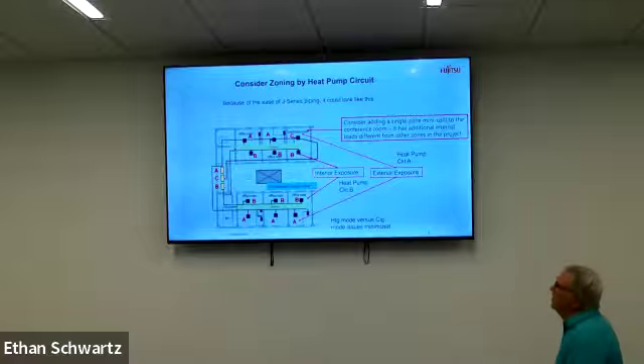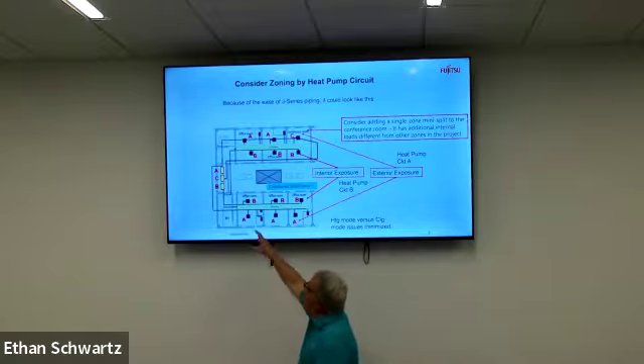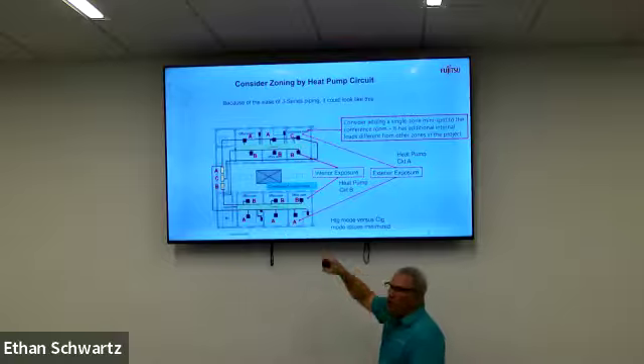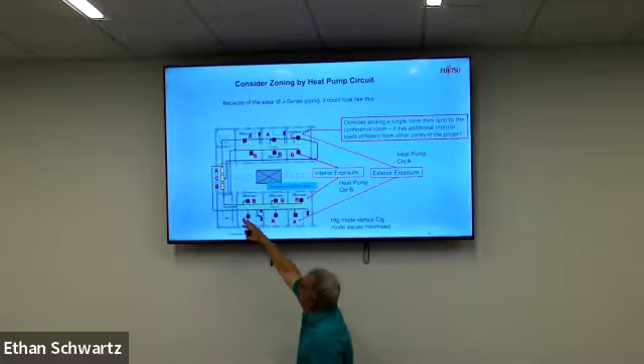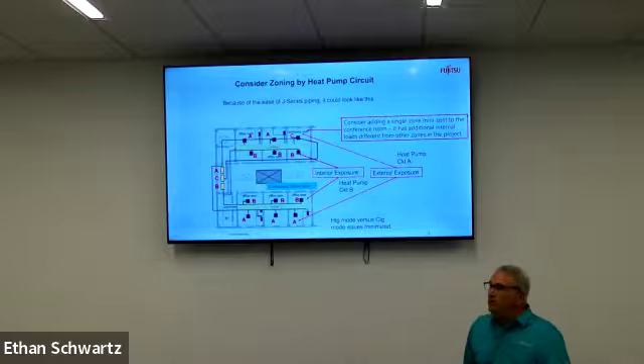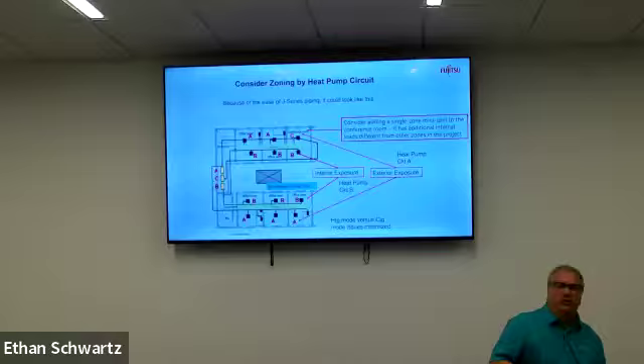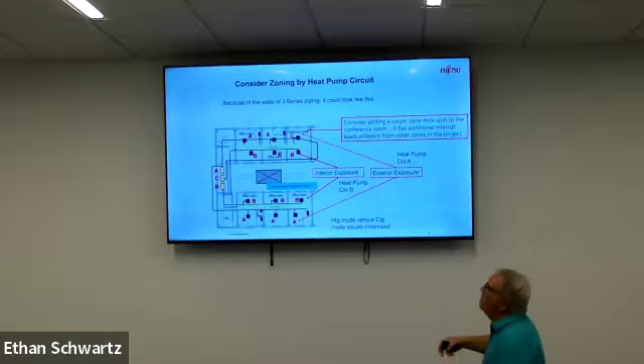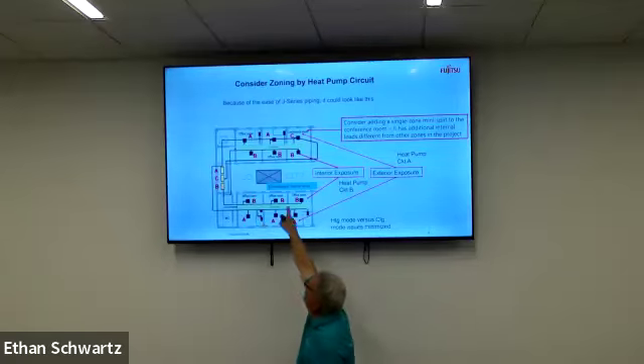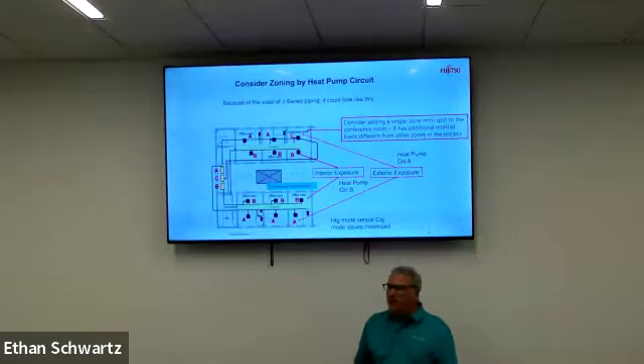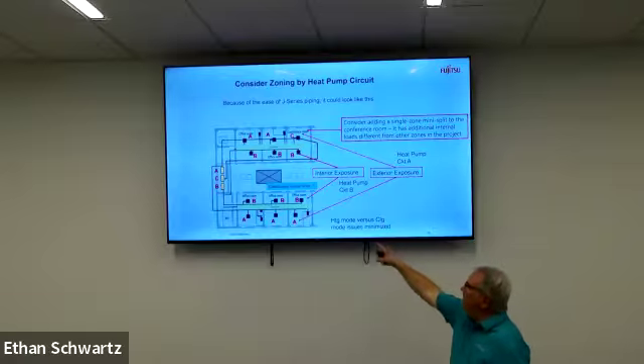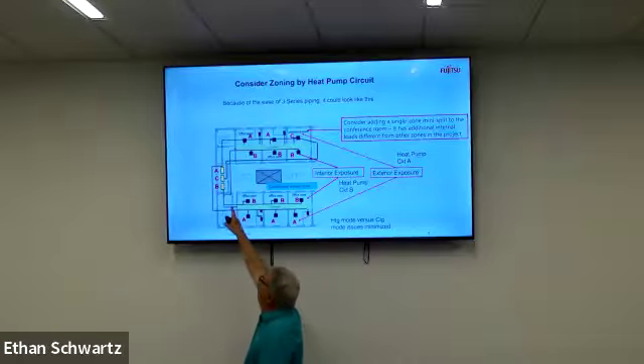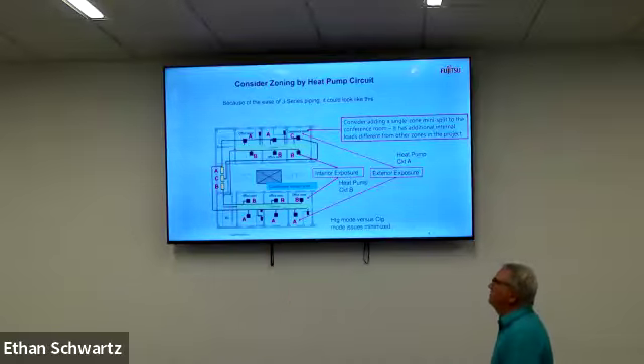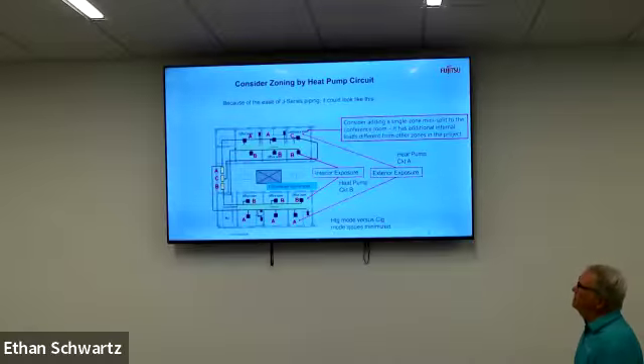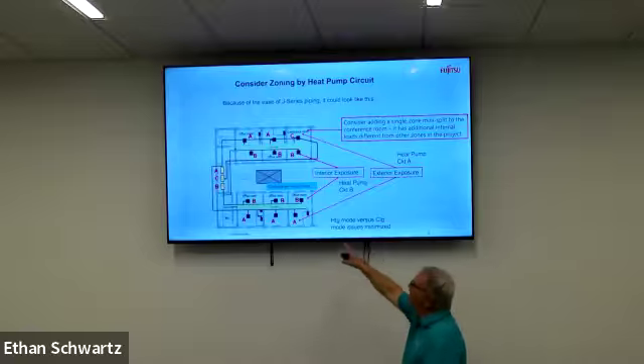But then we look at that same thing and say, okay, I'm going to make B my interior zoning by heat pump, assuming that these offices and those offices, now we have the corridor in there, so those offices are going to have a similar load profile. Again, we won't get into doing all of the load calculations, things like that, but my estimation is that those 3 offices are going to be very similar to when they need to go into heating and cooling. So let's put B in the interior zone, because with VRF, we can definitely do that, because we can easily handle 6 individual cassettes or wall mounts. And then we'll put A on the outside.